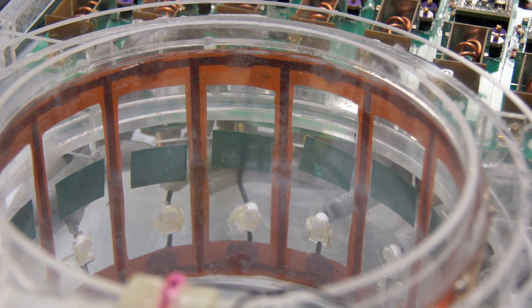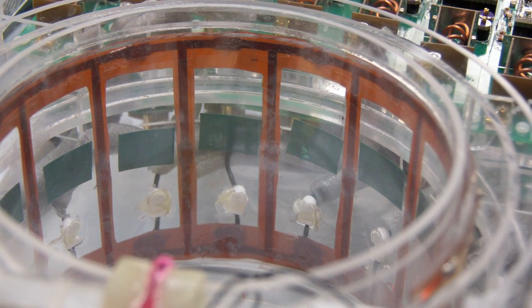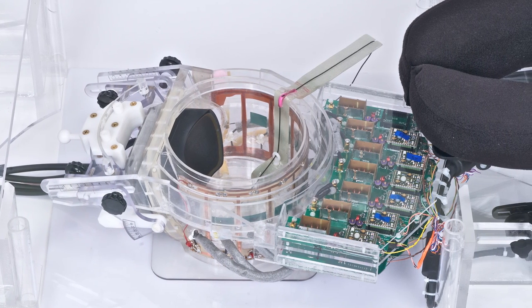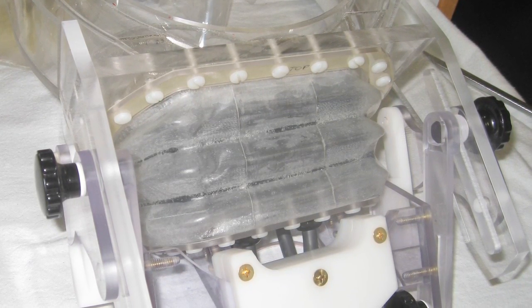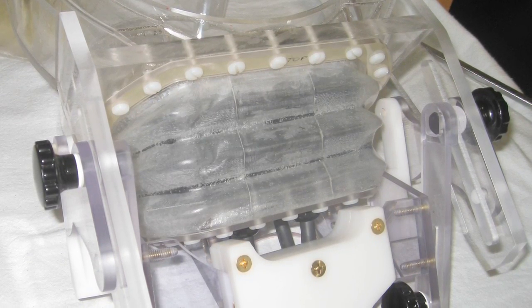It has a very small water box that the breast is suspended into, with something to pull tension on it. It's designed so that it has an array of radio frequency coils placed all the way around it, so that the image quality from the MR side is actually very, very good. It took us a while to figure out what might work, and PlastiDip worked beautifully. So it's a very flexible bellows that allows the transducer to go inside the cylinder and outside the cylinder, so you can position it wherever you need to in order to attain the target.